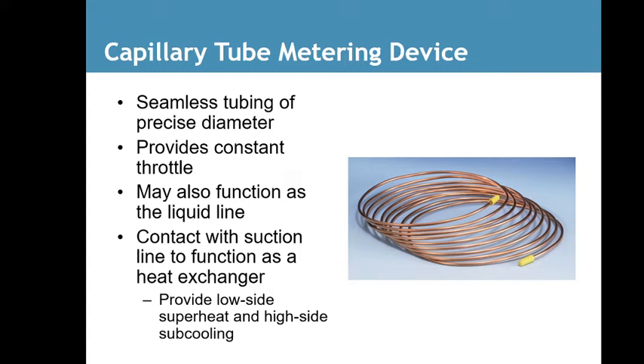Capillary tube device. Here's a capillary tube, and it's hard to understand how thick this is. But this capillary tube, the outside diameter is about the size of a number 2 pencil lead. It's very small. It's actually maybe a little bit smaller than that. The opening inside, if you had a small 1-inch piece, you probably couldn't even see light through it, because it's so small inside it would have to be ultra straight to get through it. But these have worked for many decades, and this is what we started off with.